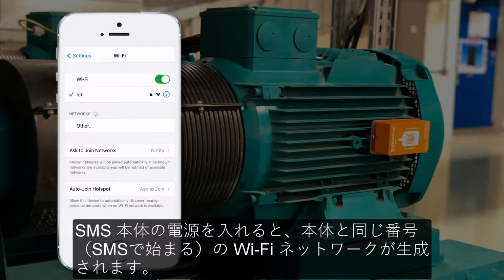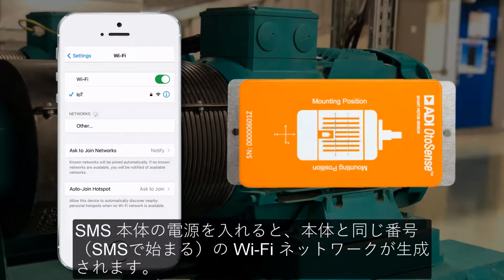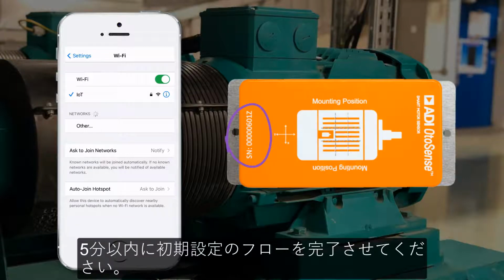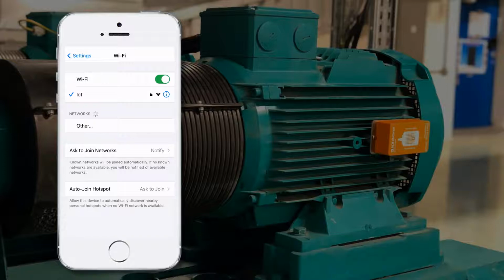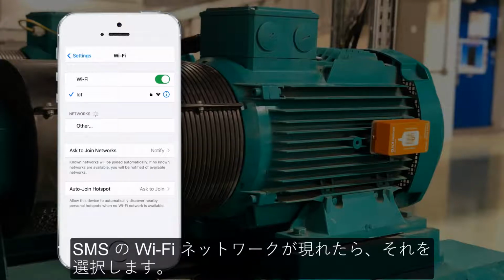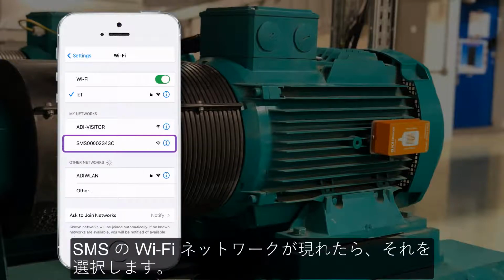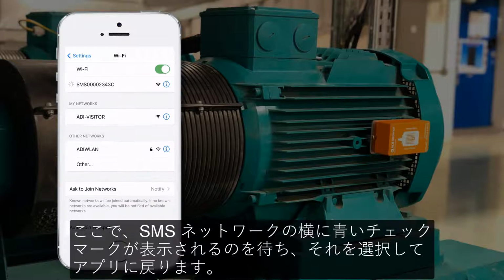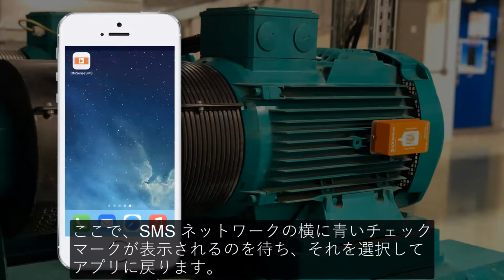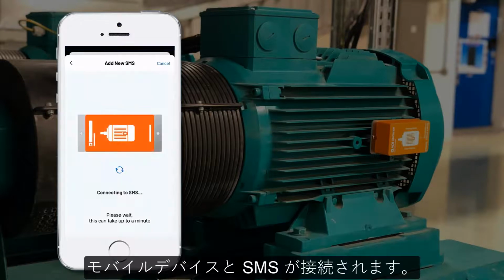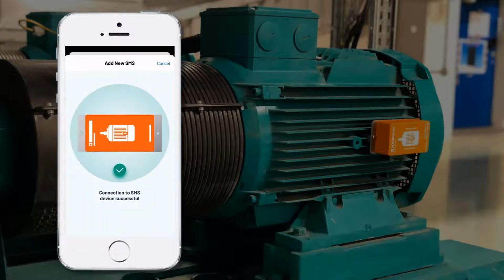Powering up the device makes it generate a Wi-Fi network with the same numbering as the device, starting with the letters SMS. You will have 5 minutes to complete the commissioning flow. Wait for your SMS device to appear, and select it. Now wait for the blue tick to appear next to the SMS network. Select it, and return to the app. Your mobile device establishes an initial connection with the SMS device.